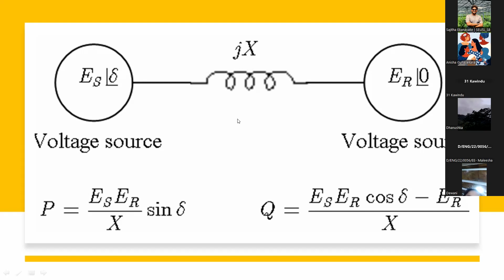When it comes to reactive power, it flows from where the voltage has a higher magnitude to where it has a lower magnitude. It only considers the voltage magnitude. So let's say at this bus bar, 220 volts becomes 230, and here it's 220. The reactive power will flow from the 230 bus bar to the 220 bus bar, from higher to lower voltage magnitude. So it's possible for active power to flow in one direction and reactive power in the other direction.